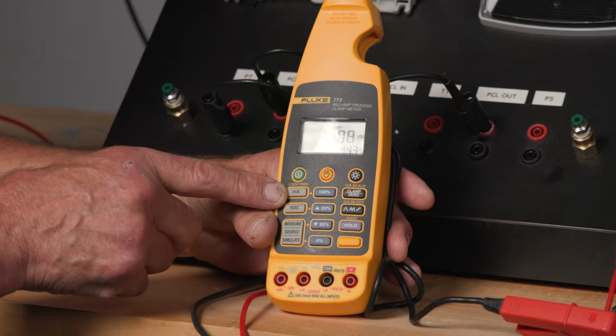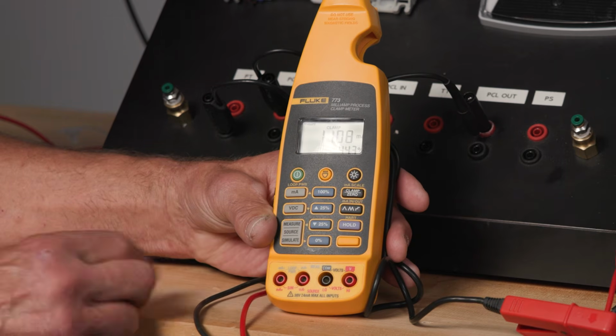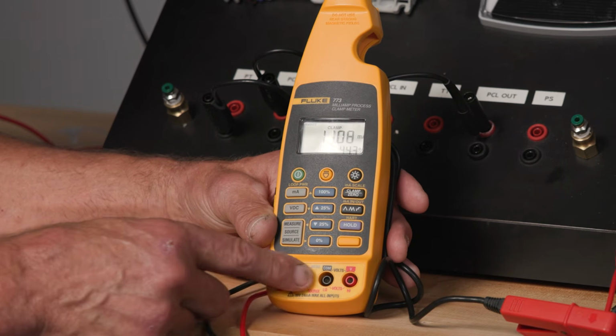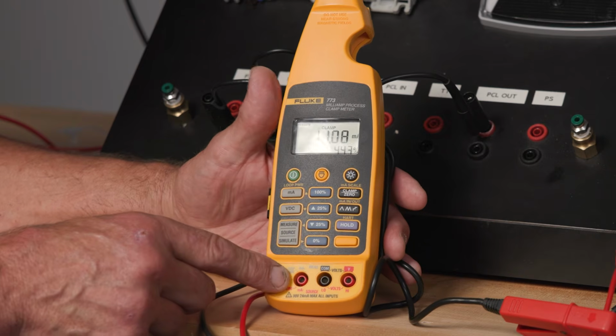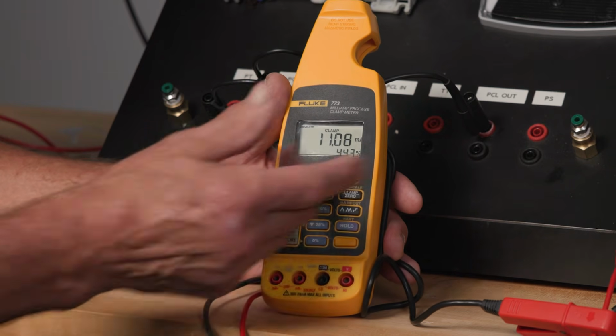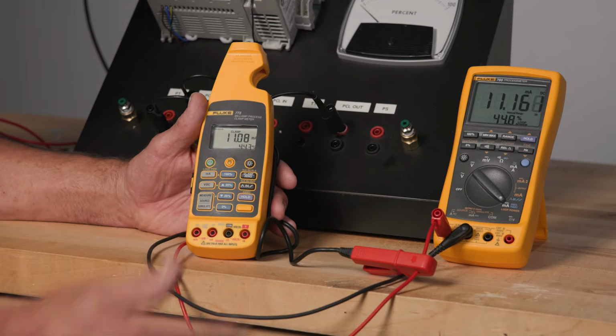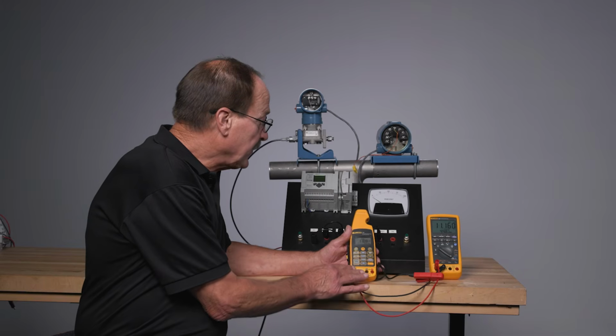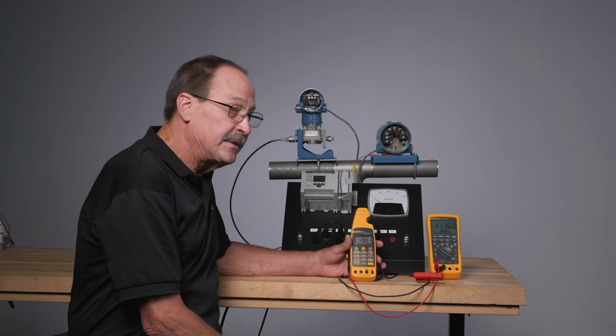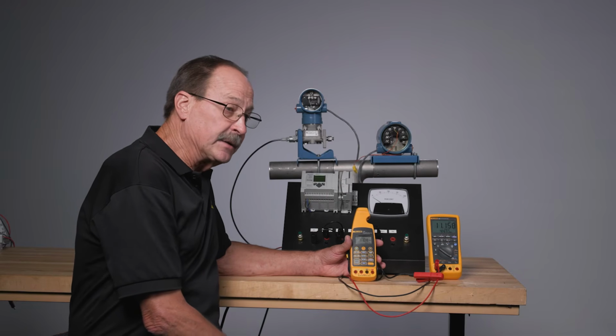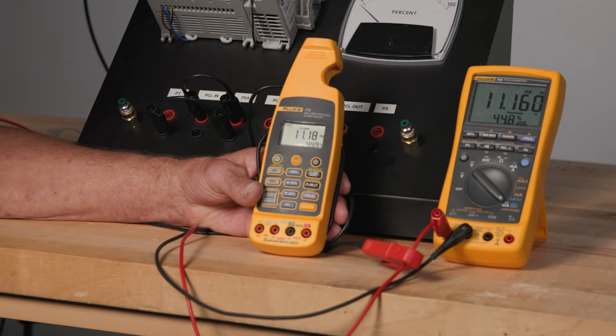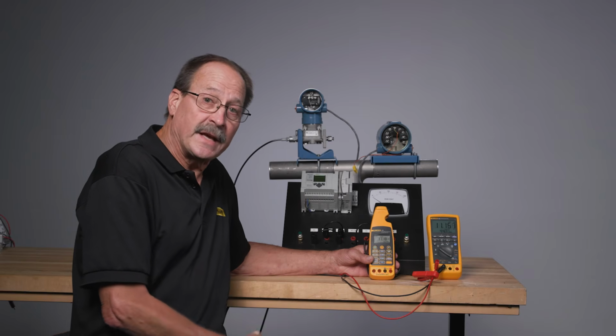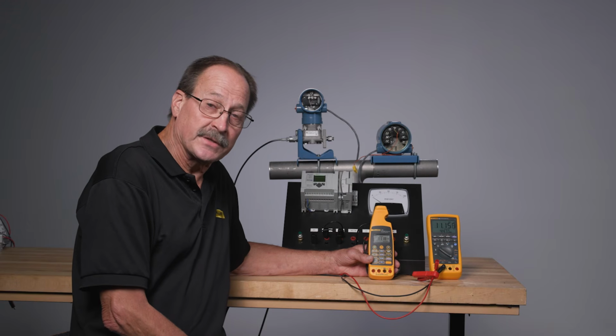The milliamps, we have the ability to source and simulate milliamps using the loop functions, and the ability to provide 24-volt loop power as this process meter is doing while powering a transmitter device. The 773 is also powerful for use in HVAC where additional 0 to 10 volt DC signals might need to be tested. The Fluke 773 Milliamp Clamp Meter measures 4 to 20 milliamp signals without breaking the loop, and is useful in HVAC applications where we need to source 0 to 10 volt signals.